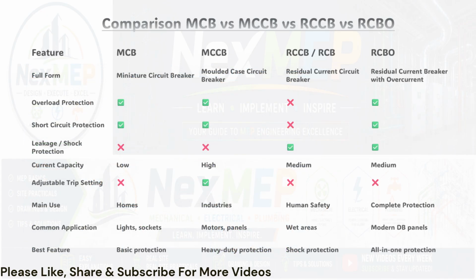Now let's bring it all together with a comparison. Looking at the table, the MCB gives you overload and short circuit protection, perfect for homes, lights, and sockets. Simple, reliable, basic. The MCCB adds high current capacity and adjustable trip settings. That's for industries, motors, and large panels. Heavy-duty protection. The RCCB only provides leakage protection. It doesn't handle overloads at all. But for wet areas and human safety, nothing beats it.